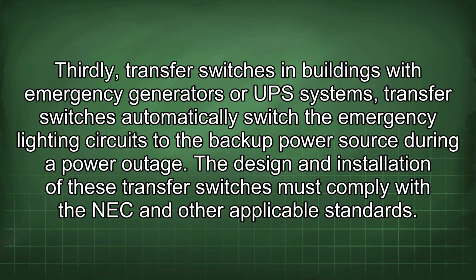Thirdly, transfer switches. In buildings with emergency generators or UPS systems, transfer switches automatically switch the emergency lighting circuits to the backup power source during a power outage. The design and installation of these transfer switches must comply with the NEC and other applicable standards.